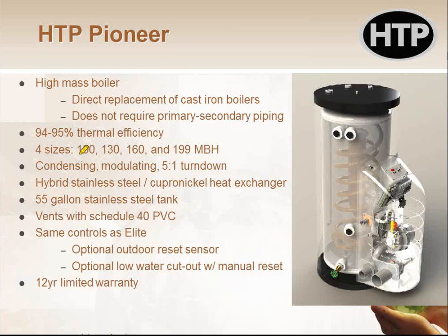Well, every time that thermostat calls for heat, my burner kicks on my low mass boiler, which is not ideal. If I use one of these high mass boilers instead and I turn on that pump and pull 2,000 BTUs out of this tank, no one's even going to know I pulled 2,000 out. My burner is not even going to have to fire. I pull 2,000 out of the 55-gallon drum, life goes on. When I get enough people calling for heat, then I'm going to have to fire my burner. So it reduces the short cycling quite a bit.